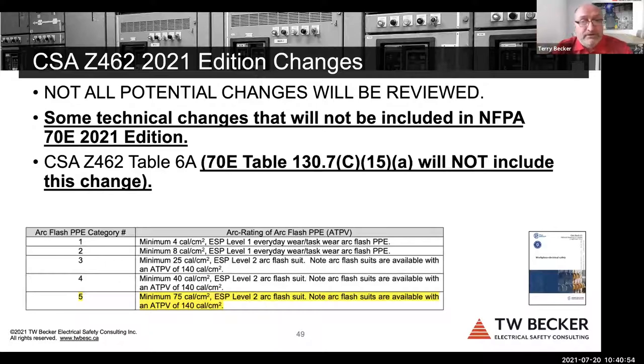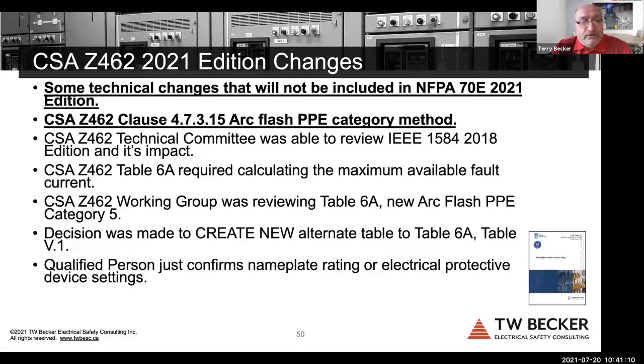If some public comments came forward to revalidate the incident energy values underneath the arc flash PPE category table method. So this is in Z462: if you don't have an engineering study, you have the tables, and you have low voltage switchgear, you're going to have a 75 cal arc flash suit. So again, we reviewed the changes and created a new alternate. When we were reviewing it, someone said, why don't we create a new table that's easier for the electrician to use? They don't have to have any fault calculations. They just look up the nameplate data.